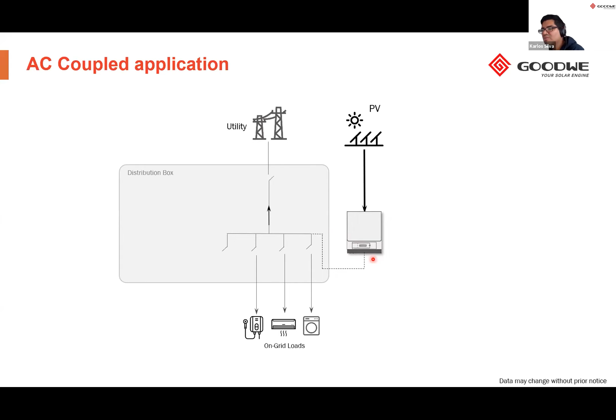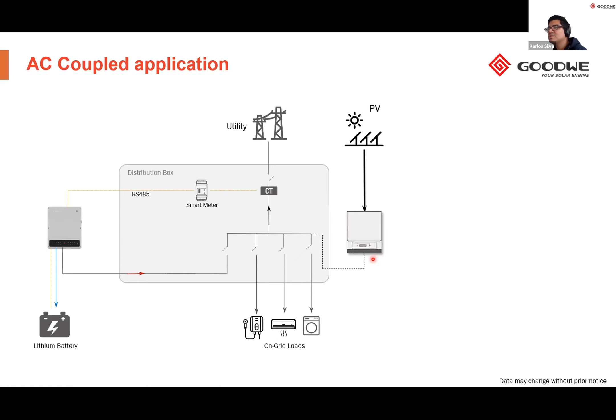In terms of the AC coupled solution, what we see here is the distribution box of the homeowner, and they may have already installed a grid connect inverter maybe 5-10 years ago. An AC coupled system is very neat to add to an existing PV system. By adding a battery inverter, you will be able to add battery storage capability to an existing system that has been installed for a number of years. This is quite neat for systems that are on a feed-in tariff. In Germany, we have many residential systems which are on a feed-in tariff for 15 to 20 years.